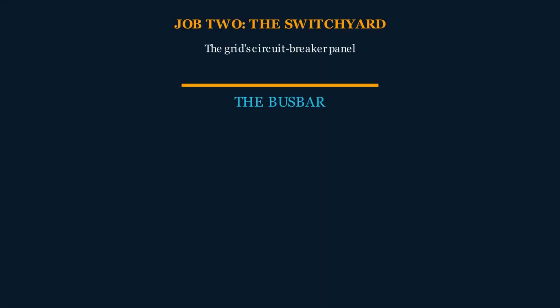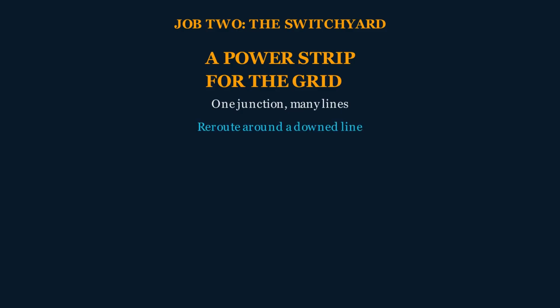Because a substation is also the grid's circuit breaker panel, the same idea as the breaker box in your basement, scaled up to the size of a parking lot. Look at all those horizontal bars and the wires connecting everything together. The central piece is the bus bar, a shared metal conductor that every incoming line and every transformer connects to. Picture a power strip for the grid. Instead of one line feeding one transformer feeding one street, the bus bar is a common junction where several lines and several transformers all tie together, so power can be routed from any source to any destination. If one line goes down, the bus bar lets the substation feed your neighborhood from a different one.